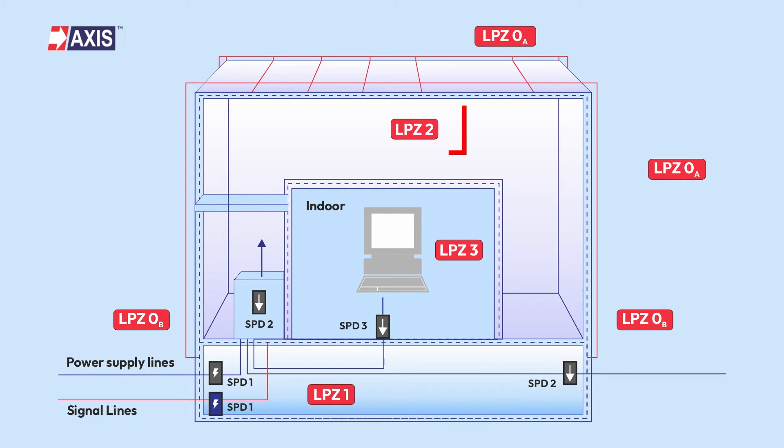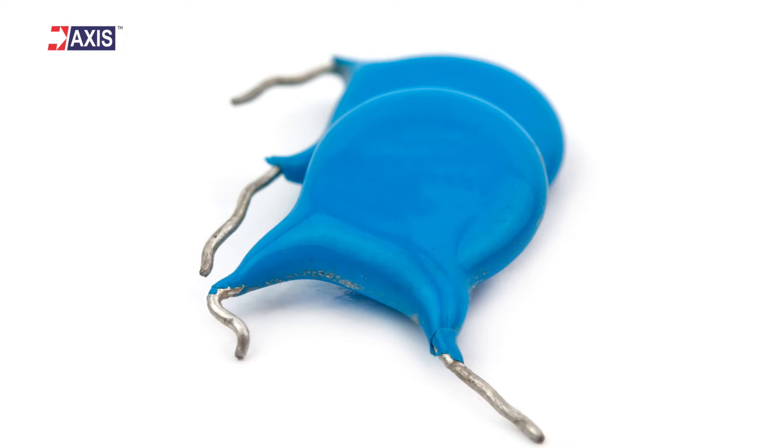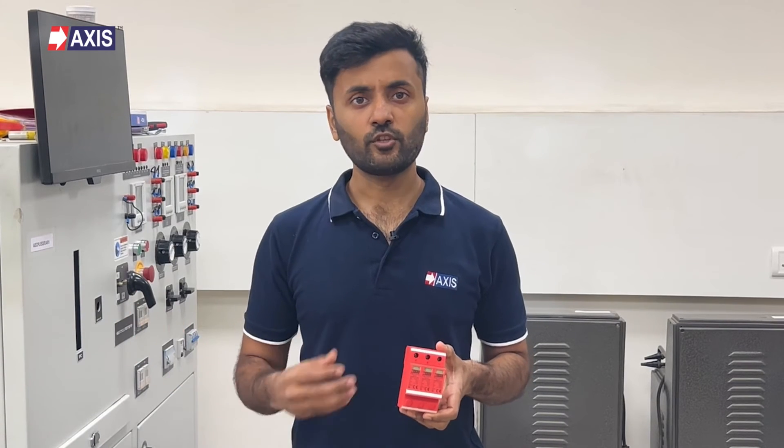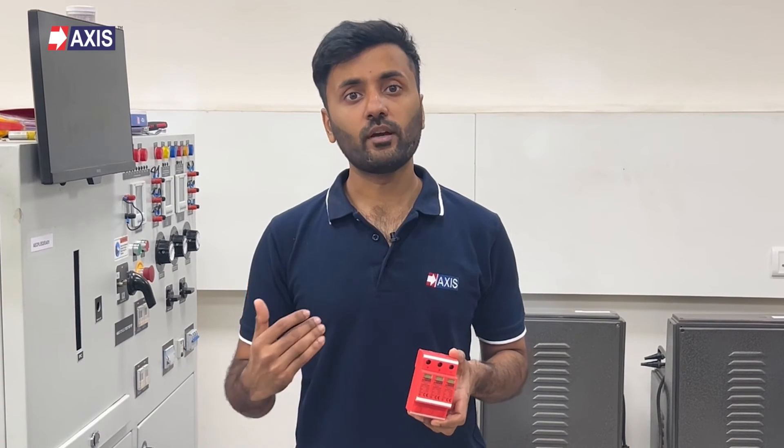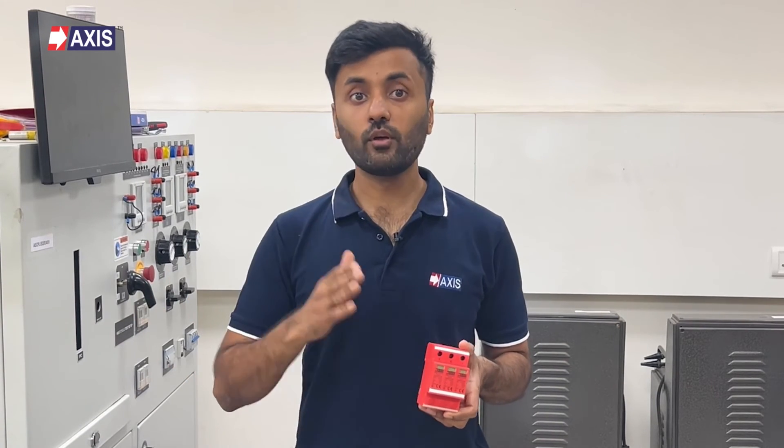Type 2 SPDs, also known as class C SPDs, are recommended in LPZ2 areas. Their main function is to handle switching surges. These SPDs are made from MOV — a metal oxide varistor — an electrical component whose resistance varies with the voltage. Type 2 SPDs respond faster than Type 1, but they have a lower energy handling capacity. Therefore, we recommend installing Type 2 SPDs in distribution panels that follow the main panel where the Type 1 SPD is installed.